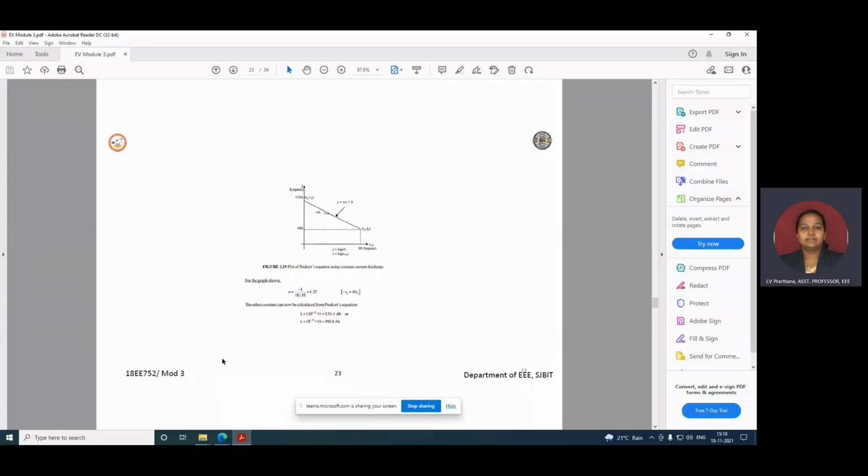Manufacturers specify the capacity of the battery at a specified discharge rate. For example, a battery might be 100 Ah when discharged at the rate that will fully discharge the battery in 20 hours. If discharged at a faster rate, the delivered capacity is less. Peukert's law describes a power relationship between the discharge current and the delivered capacity. Over some specified range of discharge current, if Peukert's constant k, the exponent, was equal to unity, the delivered capacity would be independent of the current. For a real battery, the exponent is greater than unity and capacity decreases as discharge rate increases.